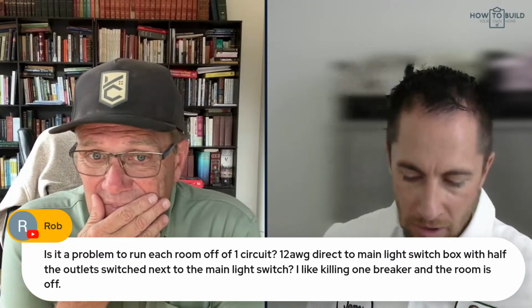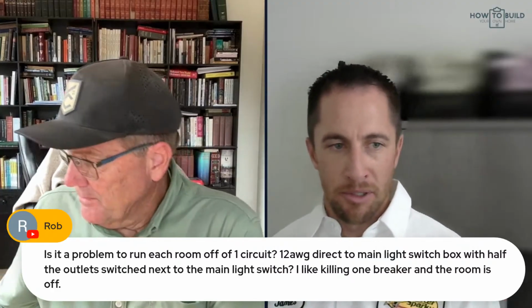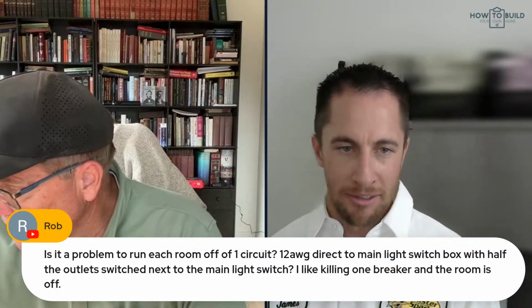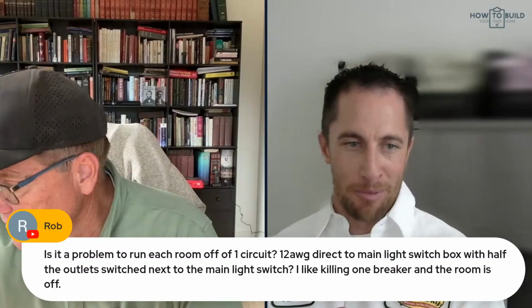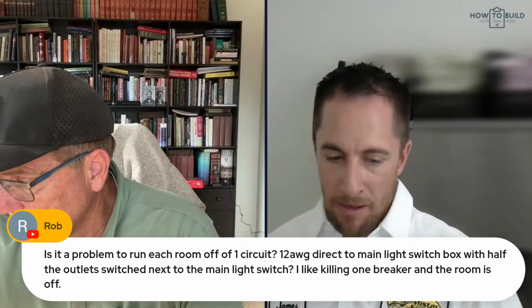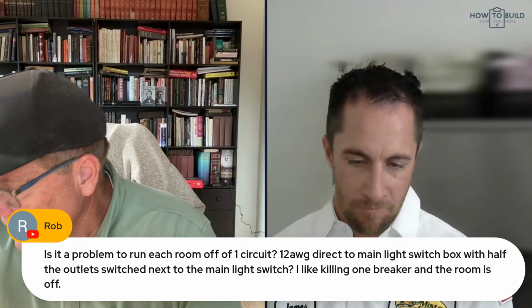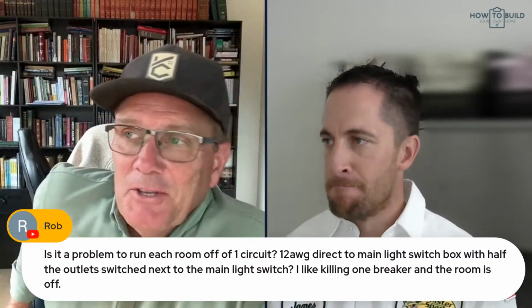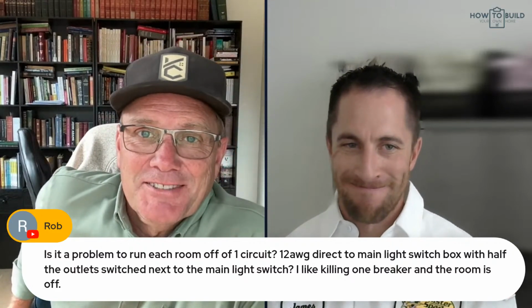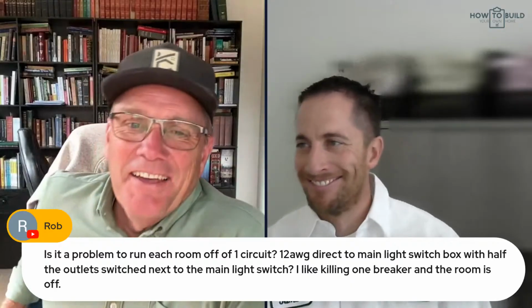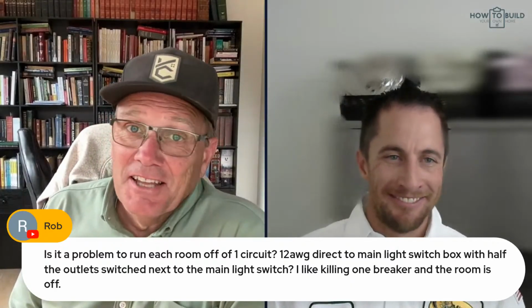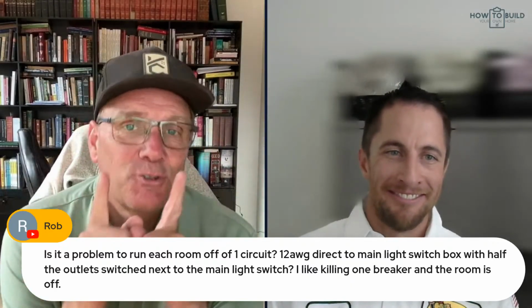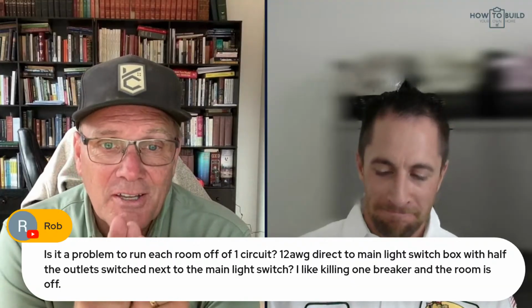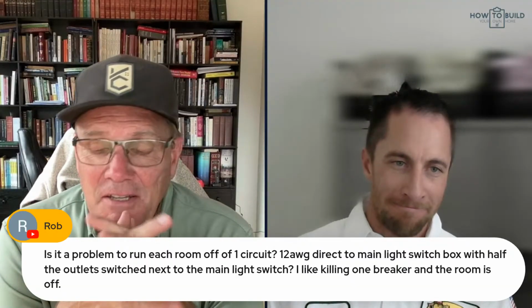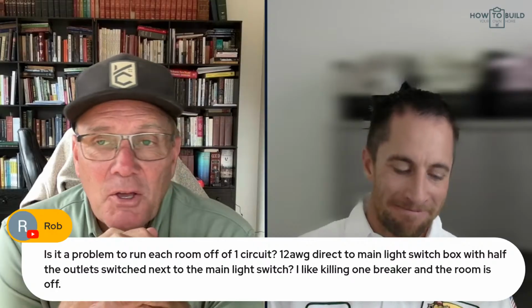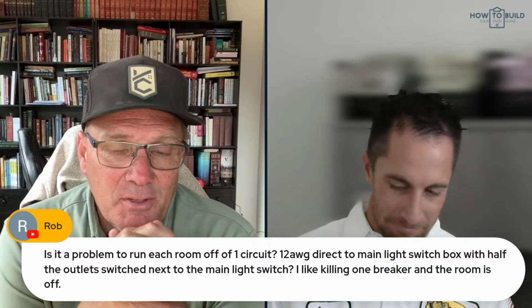If you're doing a switched outlet, make sure you use 12-3 to run to those outlets, because one will be for constant power and one will be for your switch. Right. If you're doing electrical yourself, 3-way switches are going to be a beast. And GFIs, line in, load out. If you don't get that right, those are the 2 mistakes that owner builders make all the time. James, explain on the GFI what line in and load out basically means, so people can learn what that is.